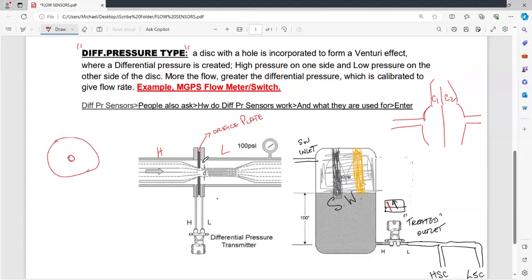So if this orifice plate was not there, then the pressure on this side and the pressure on this side of the flange are both going to be equal. You will not be able to have a differential pressure that is going to then be converted into this flow rate. So by having this orifice plate in between, it stands to reason that if the flow is higher, then your pressure over here is going to increase as compared to the pressure on this side. So you will be having a higher pressure this side as compared to this side. So this differential is then going to be moving this particular meter more to the right or towards the left, depending on the flow. Okay?